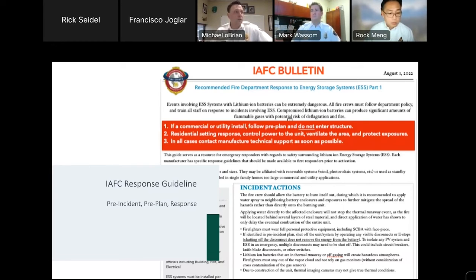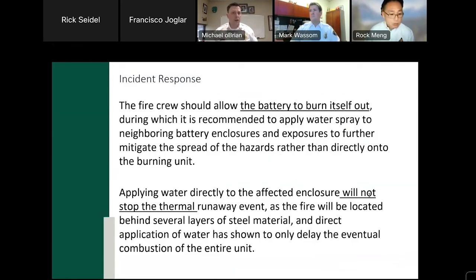And where it gets different for us in the fire service and this responding, we heard about the testing, the HMA, and all the things that take place before we get a unit installed. But the foundation for how all of those are occurring is in this large scale fire testing, where we see how that unit responds. Each manufacturer, with their design team and their protection measures, starts to elaborate how a unit is to take care of itself when a cell goes into an event or is starting into thermal runaway. And the hardest part for us in the fire service is that you could have different manufacturers and different locations with different strategies in the engineering and design process. So it's vital, as we shape our response, that we as the fire service understand the design implications, how the systems were intended to be used, and what was within the design. Next slide.